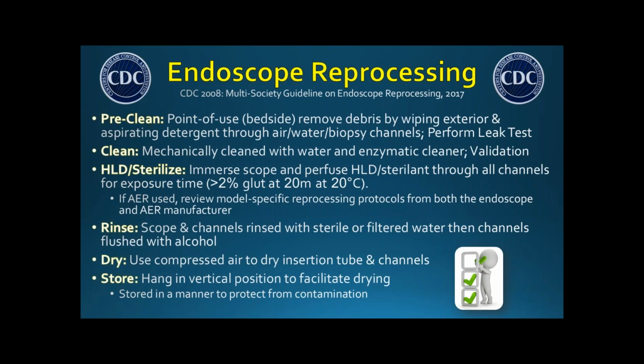so that you can see how to properly ensure that those are cleaned, especially the connectors that go onto your endoscopes. You want to make sure that those get cleaned and processed every once in a while as well, because it is water and channels that run through it. So they do have recommendations on how frequently you need to put those through high-level disinfection, whether it be through OPA or some other methodology.